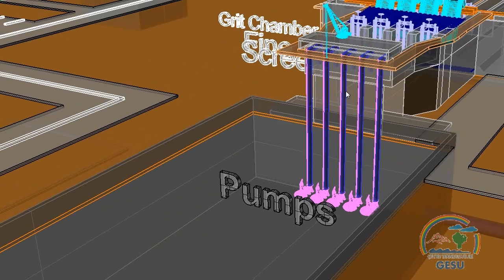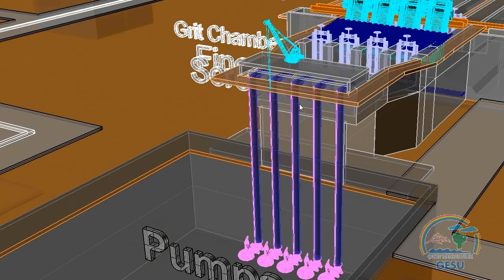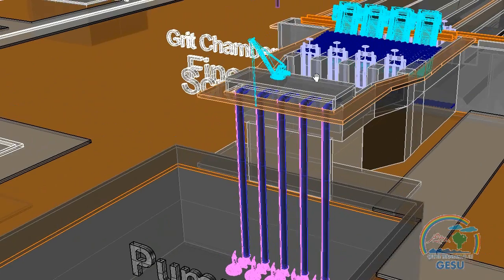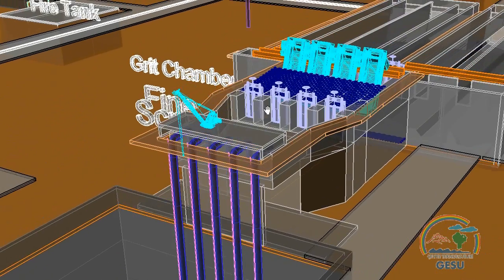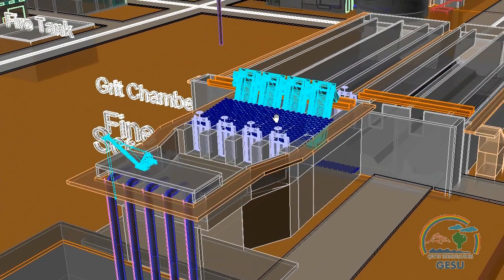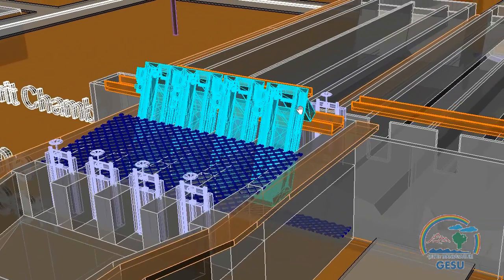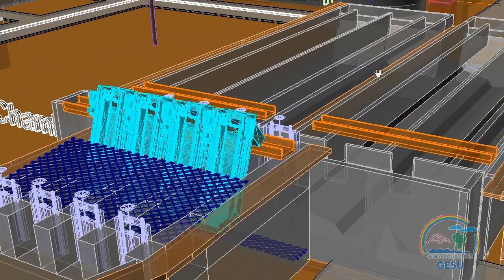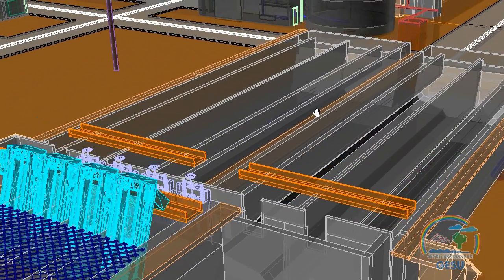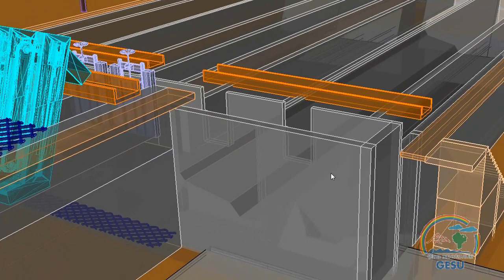Water level is increased by 10.5 meters using 5 submersible pumps and continues to the fine screen unit. Small particles are captured with 4 screens, each having 1 cm bar openings.